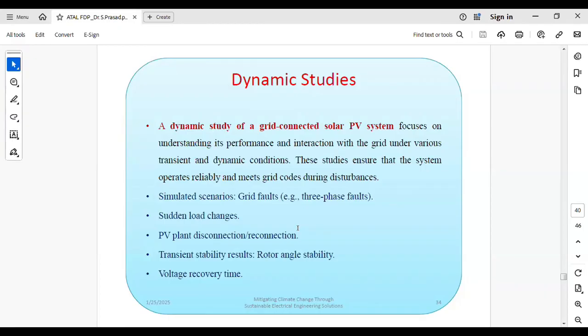Because when there is a fault at the grid end, the voltage will go down. If the voltage goes down, your plant should not be disconnected from the grid. Okay, so then collapse may happen. So up to what time you have to remain connected with the grid is specified by the CEA. And within that time, what is happening in the PV plant and at the grid end, that we have to analyze.